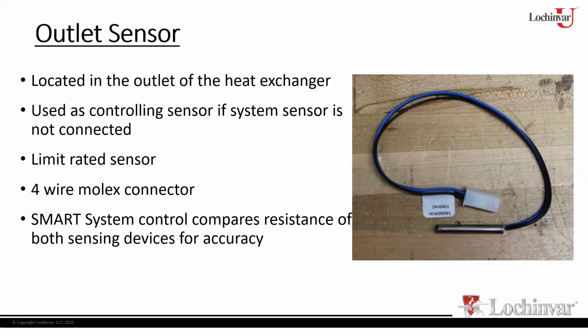It says, all right, that one sensor tells me it's 150, but I really don't know it's 150 because what if the sensor's wrong? So in this case, we have to use a check system. So here you've got two thermistors, and the control module is going to compare both thermistors. All right, one's a 10K, one's a 100K. So basically, I'm going to look at them. They have to be within 10 degrees of one another. So I'm going to give you a little bit of tolerance there. They've got to be within 10 degrees of one another.